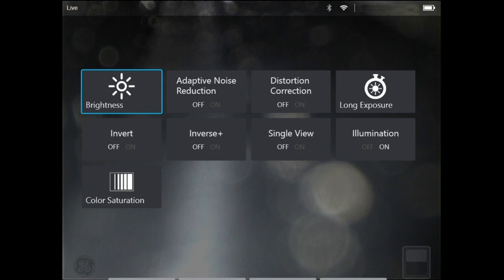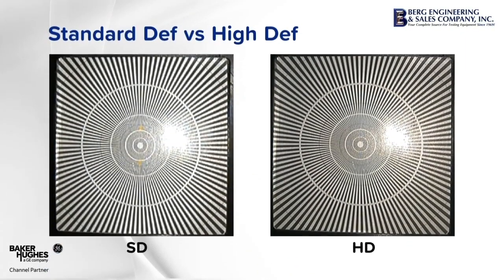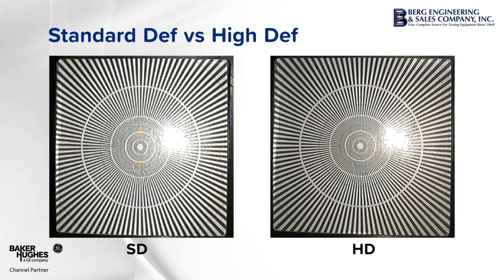But let's go back to what Tom was talking about on the high def and on the ability to resolve smaller targets on the next slide. And so you'll notice when you're looking at this, this is a starburst pattern with a standard def camera on the left. If you look at the white dot in the middle, start moving from the center out to the edges, I truly can't resolve the difference in the line pairs until I'm beyond the first, second, somewhere around the middle of the third starburst pattern can I start to resolve the target and know that there's separation in those line pairs. And then when you get all the way out to the edge of the starburst, you'll notice pixelation in the target. Whereas if you go over to the HD image on the right, I can absolutely resolve line pairs just outside of the second white ring. And you go all the way out to the edge of the image and you're not seeing any pixelation. So this is an untouched image without zoom on.